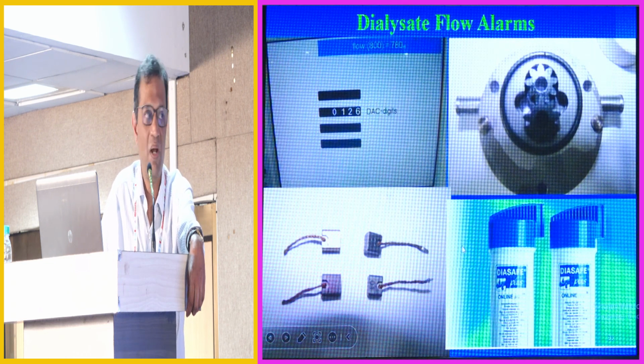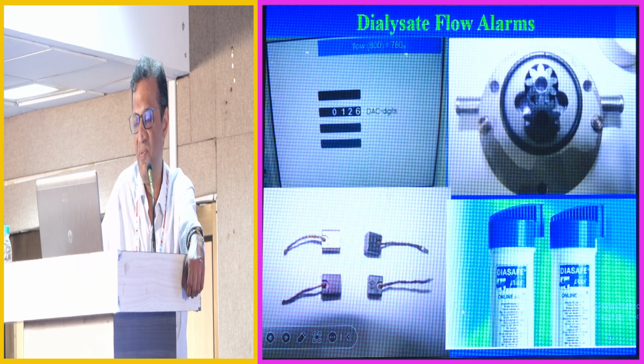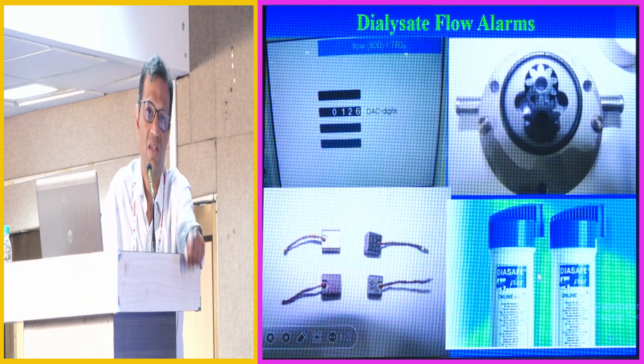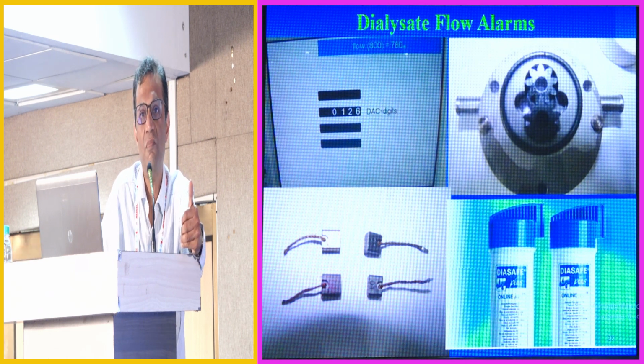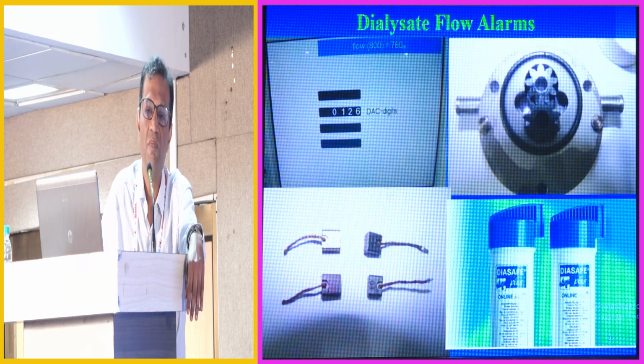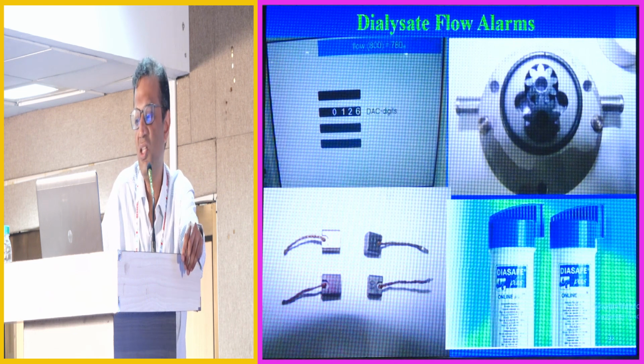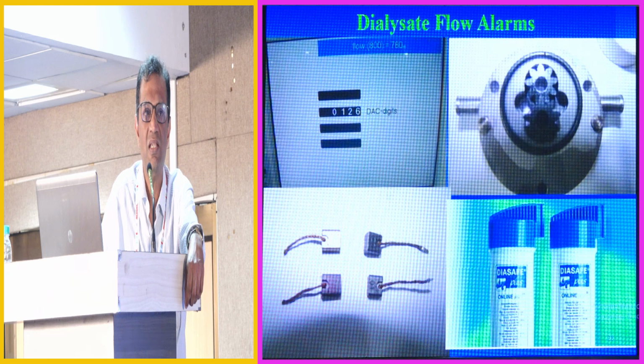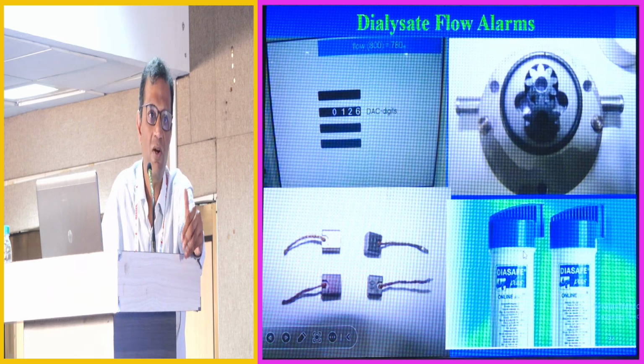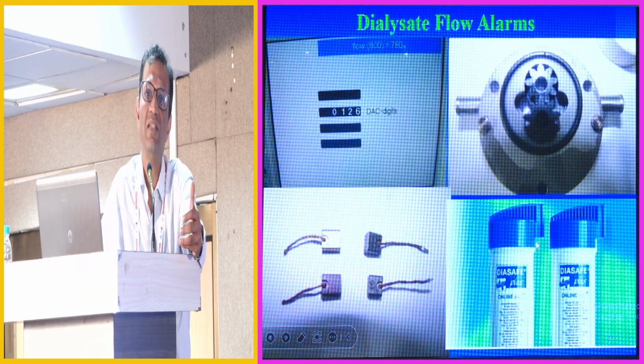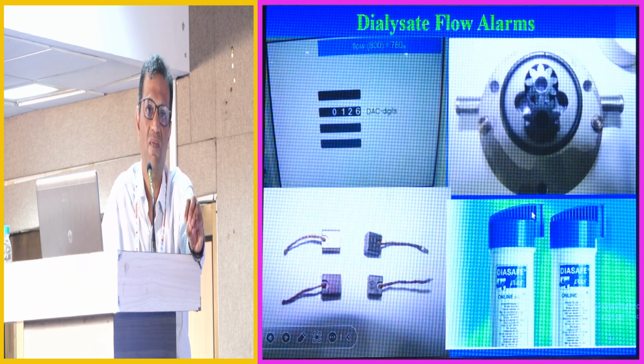This is the Diasafe Plus, or the endotoxin filter, which is placed by Fresenius in the flow path of the dialysate. This is the path which offers the highest resistance. It has a pore size of 0.05 microns, and it operates in cross flow mode. If the machine has not been periodically rinsed and decalcified with heated citric acid at least once in a day, calcium carbonate precipitates will form in the Diasafe filter. Over the life of the filter, which Fresenius says is 400 hours, or 3 months if less than 400 hours by that time, the filter pores may get clogged. But it may happen much faster if precipitates form, and in that case a flow alarm signal will be seen.